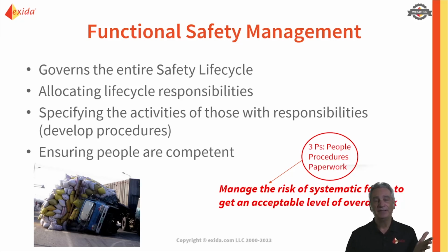The first one being the people, the competency aspect. Another major change in the 2016 edition of 511 was the emphasis on personnel competency and having well-defined roles and responsibilities. So making sure our people are trained and competent to carry out the tasks for which they've been assigned. And this means that we also have to do periodic, the standard uses the term periodic, assessments on the personnel. So first P, people. Are they properly trained, qualified and competent to do the work?